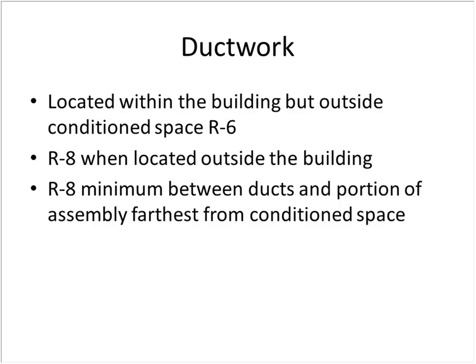And the same thing with floors. If you've got a cantilevered floor over the garage space, or a sunroom, four-season sunroom that goes out, and you've got a duct run in there, you have to have a minimum R8 into that space. Now, since it is considered outside, that would also trigger the requirement that you have your ducts leak tested, total leakage to the outdoors. And we'll talk about that in a slide or two coming up.